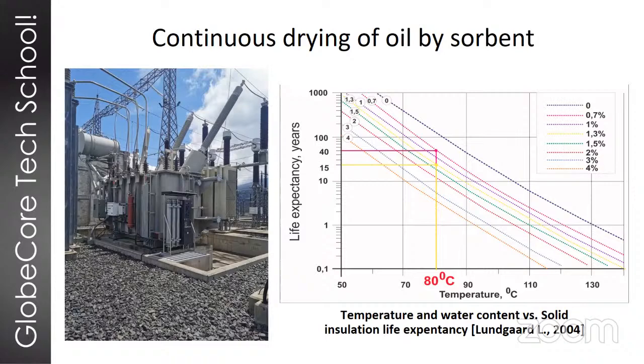So there is a practical case that we've had in South America, I believe, using GlobeCore made sorbents for 8 months. What we got was an absolute content of water in the oil reduced from 25 to 14 ppm, and relative humidity of oil was reduced from 16.9 to 9.3% at the average transformer running temperature. And what is perhaps the most important is that the humidity of solid insulation dropped from 1.3 to 0.7%.